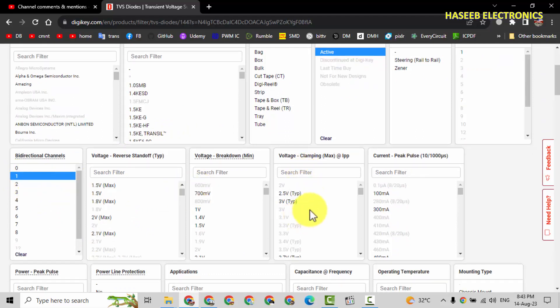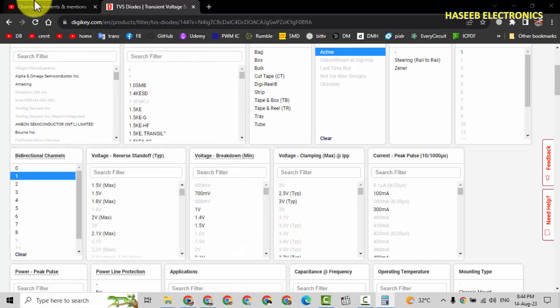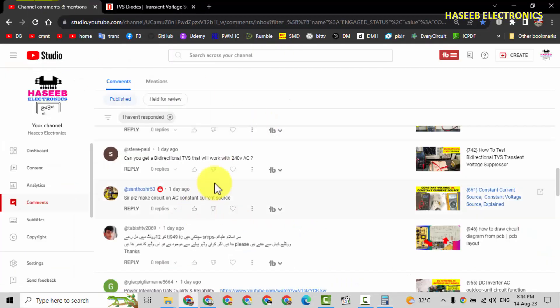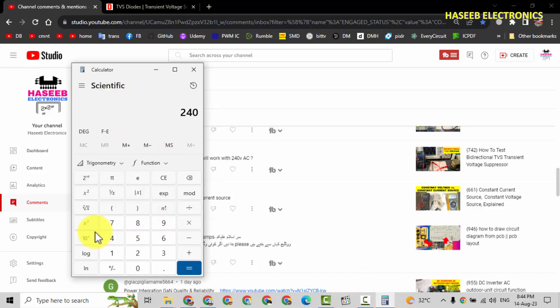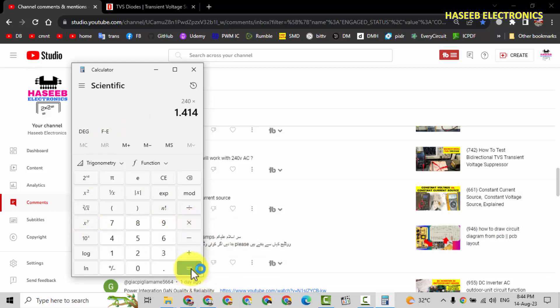We need clamping voltage. Open calculator. My friend is asking for 240V AC. 240 multiply with 1.414 to find the peak voltage, that are 339V. So this is the minimum level that we will select for clamping voltage.